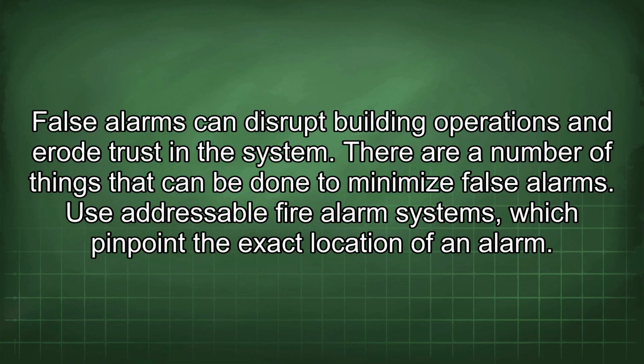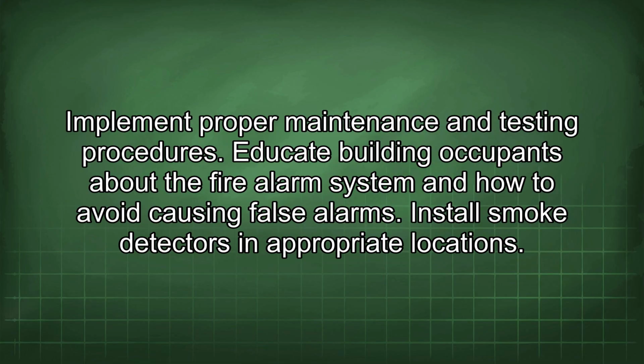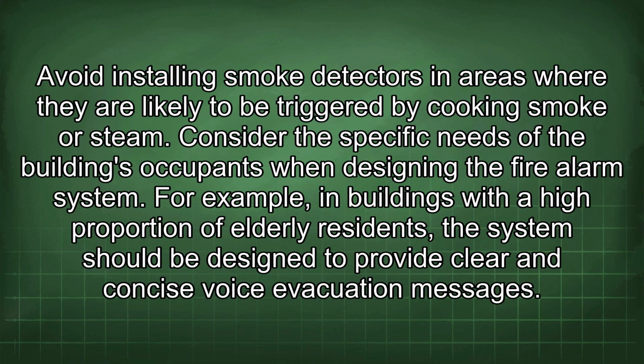Use addressable fire alarm systems, which pinpoint the exact location of an alarm. Implement proper maintenance and testing procedures. Educate building occupants about the fire alarm system and how to avoid causing false alarms. Install smoke detectors in appropriate locations. Avoid installing smoke detectors in areas where they are likely to be triggered by cooking smoke or steam.